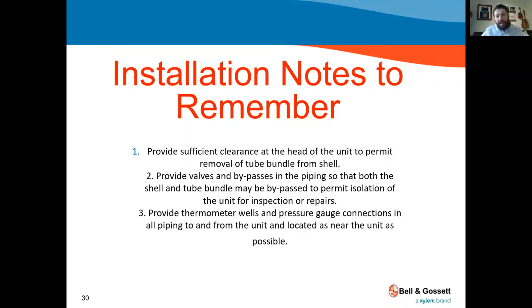Provide the valves and bypasses, so piping, so that both the shell and tube bundle may be bypassed to permit isolation of the unit for inspection or repairs. And thermometer wells and pressure gauge connections, all piping to and from the unit located as near the unit as possible.